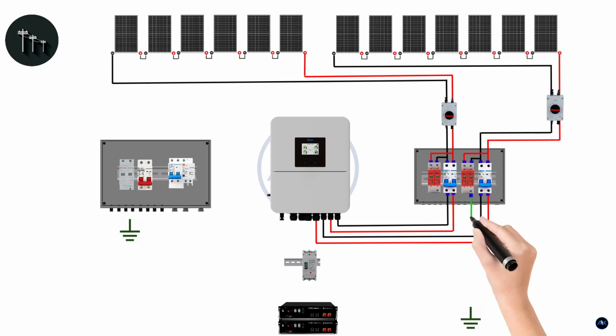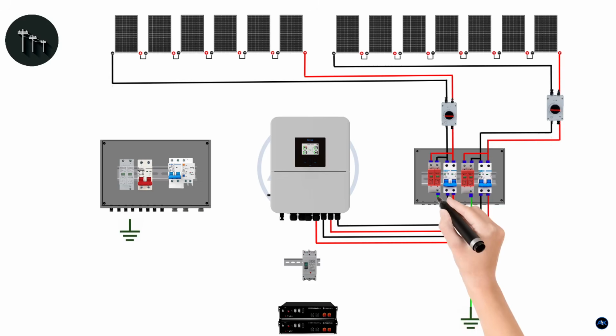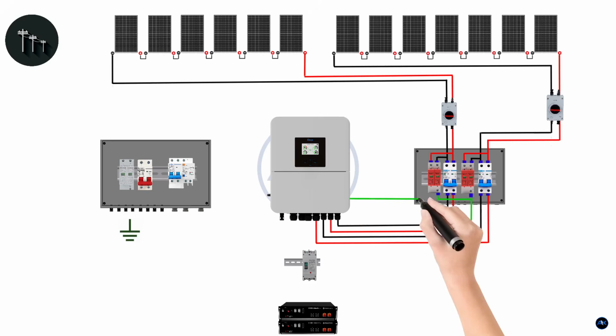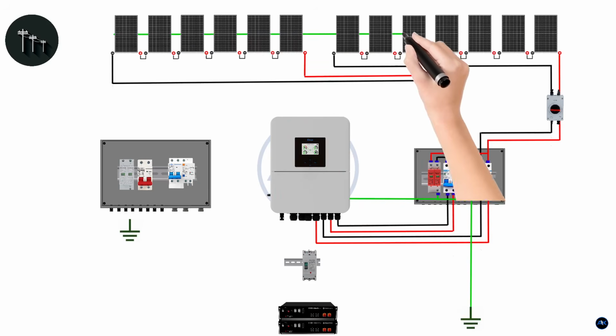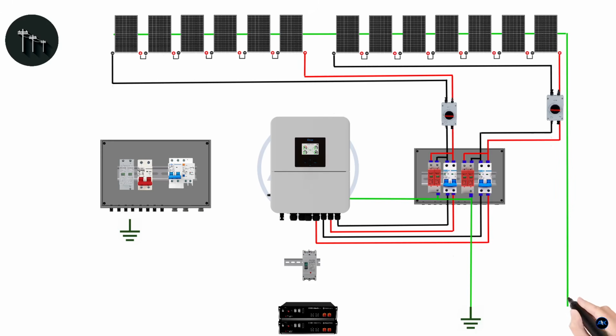MC4 Y connectors. Run the main positive and negative DC cables from your solar array, or combiner box if you have multiple strings, to your DC-DB. Connect these to the input terminals of your DC isolator or surge protective device within the DC-DB. Connect the output of the DC-DB to the PV input terminals of your hybrid inverter.